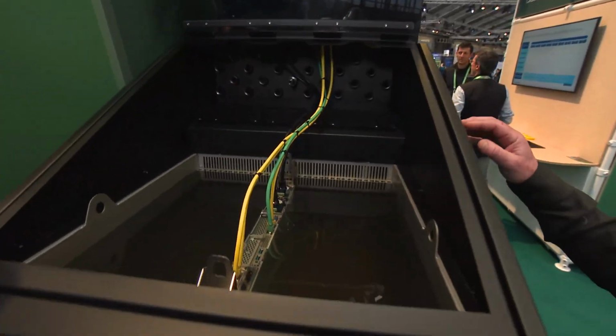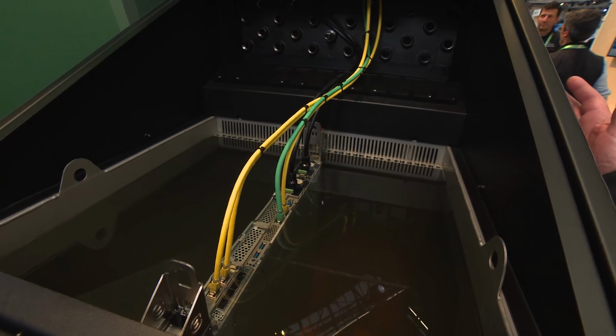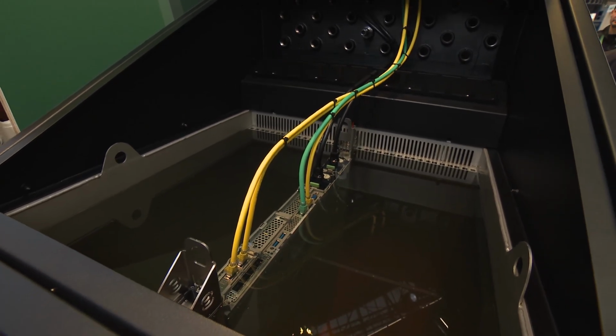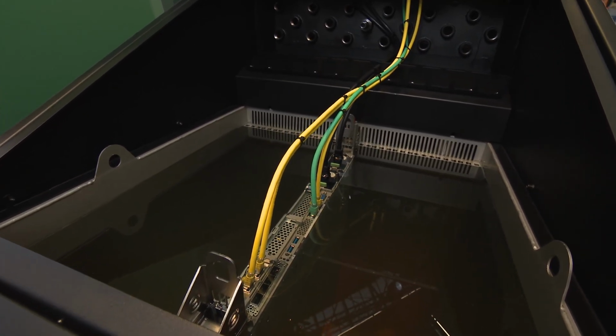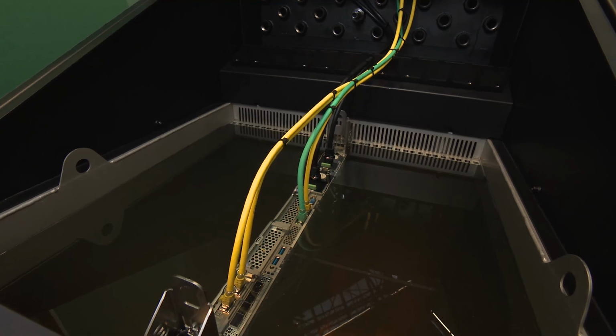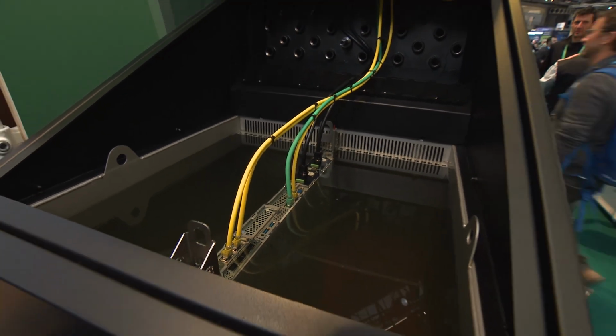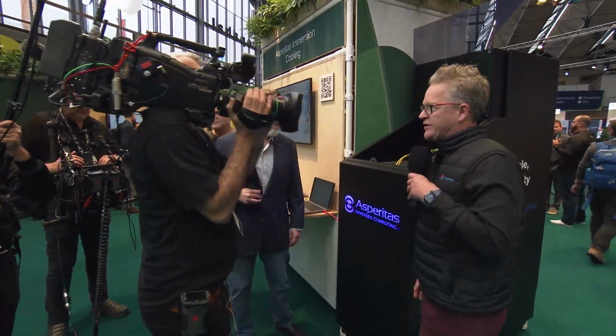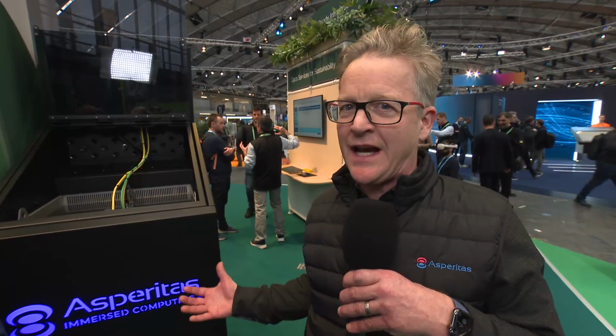So you can see here the server immersed - it's a single server to demonstrate its operation. We have cooling circulating from below, cooling up to 5 kilowatts per U - that's a 1U server right there. We can have additional cooling from the top using targeted flow to achieve up to and in excess of 1 kilowatt per chip, which will be able to cool your workloads in the future for AI with a minimum of power overhead. Literally 60 kilowatts with a few hundred watts for the pumping circulation of the dielectric, and that's it. So super efficient, super compact.